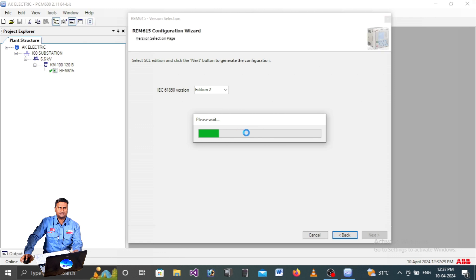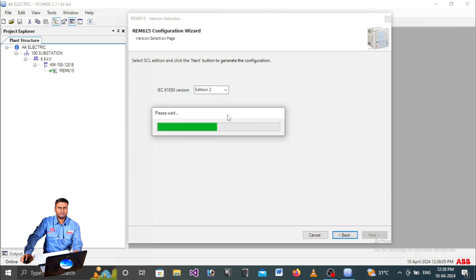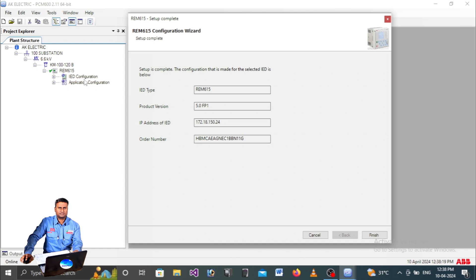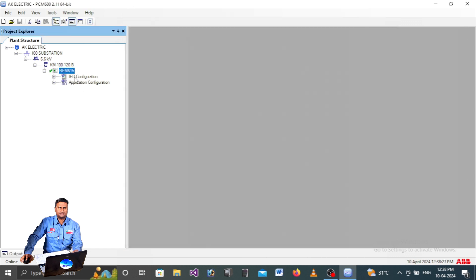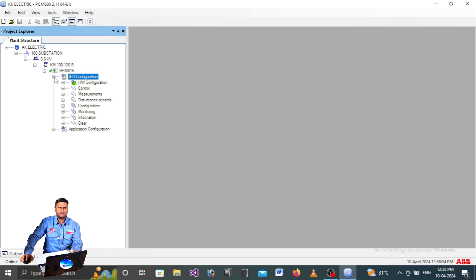PCM software is communicating with the relay to get default information. It takes about one to one and a half minutes. Once complete, you will receive two configurations: IED Configuration and Application Configuration. The setup is complete - click Finish. To explore IED configuration, click the plus symbol to expand it, where you will find hardware configuration, control, measurements, disturbance records, and more.